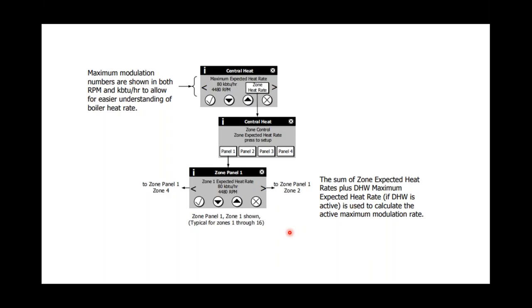If you ever have any question whether it's hooked up to a 4 to 20 milliamp system or 0 to 10 volt DC, and for some reason the boiler is not turning on or not responding, on any of the products, if you jump the DHW terminal, it will always fire for domestic hot water, unless there's an error or something seriously wrong. But it will quickly let you know whether it's an issue with the boiler or whether it's an issue with the external system.